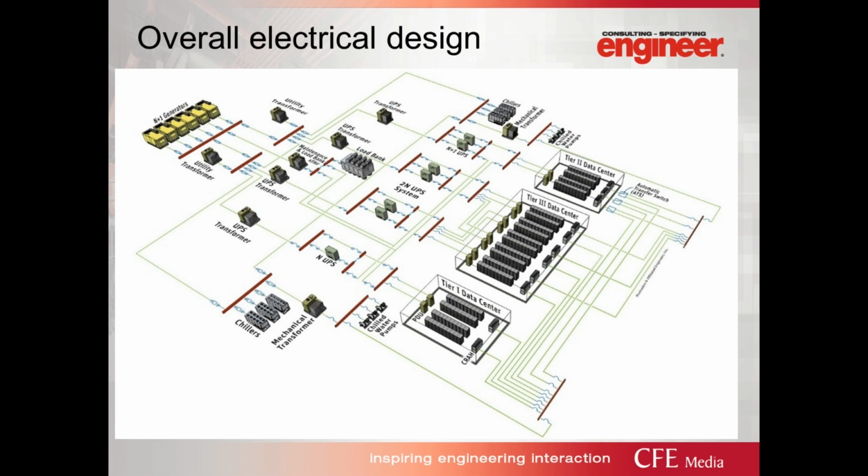And lastly, what are you looking at? Automation and monitoring. In my experience, people are monitoring just about everything for the data center infrastructure. And we're talking about an EPMS, electrical power monitoring system. In the computer floor, or the white space as we call it, we talk about a DCIM system. You also have your building automation system that you map data points to as well.